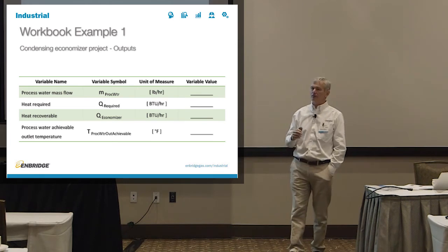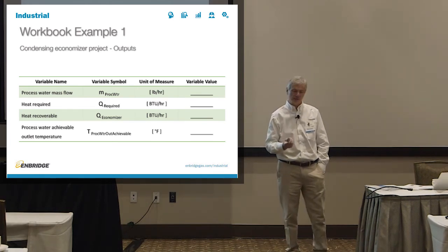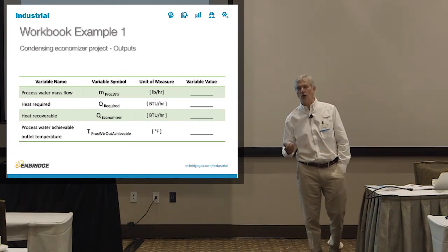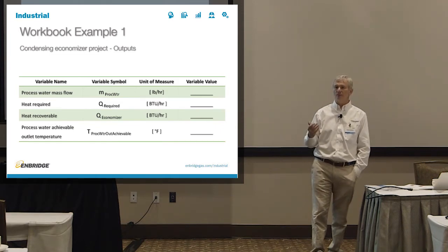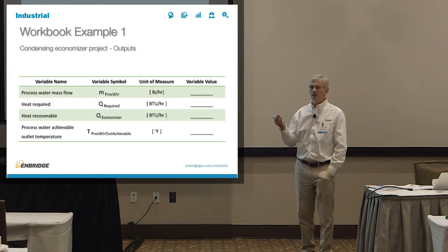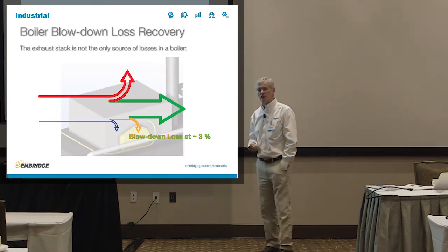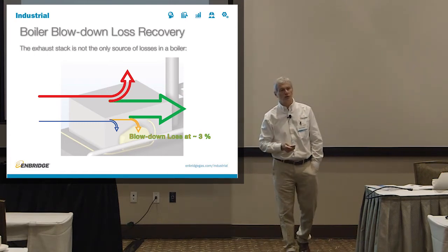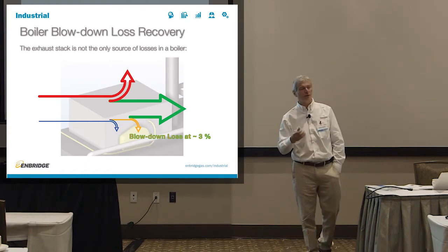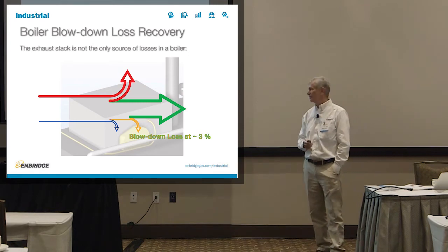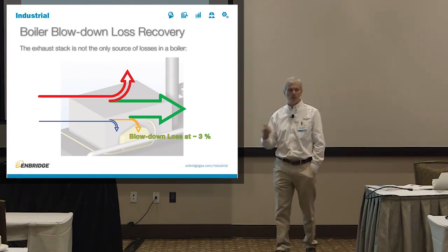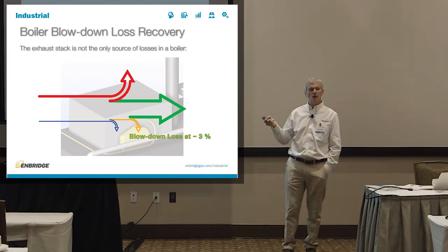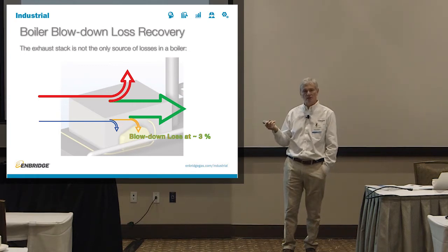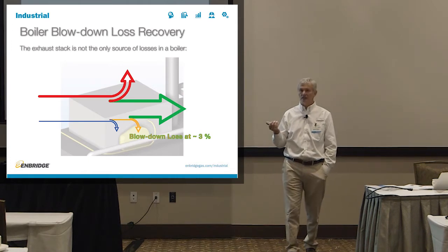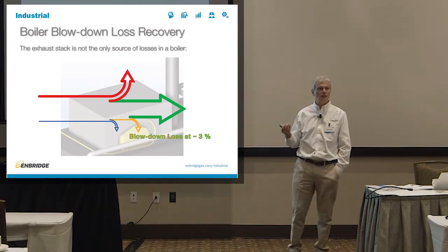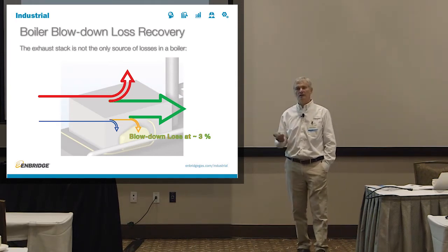We have managed to get our thinking around how to recover the heat from the boiler flue gases. And I started with that for a reason, because about 20 to 25% of the energy put into the boilers will actually go up the stack, literally in flames. But there are also other sources of losses on the boiler. We mentioned them. One of them was the shell losses, which I wouldn't worry about. Unless your boiler is in really bad shape, it's usually about 0.5% to 1%. But the bigger one is the blowdown loss. I put it down here at 3%, because that's what the typical blowdown losses should be. We've seen facilities where blowdown losses were as high as 15%. We typically see facilities run blowdown loss at about 7 to 8%. If you have a big boiler, that adds up.